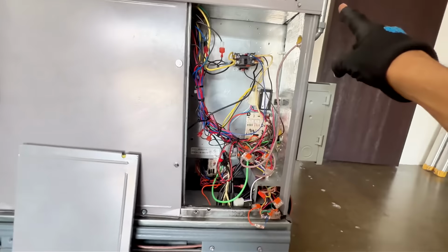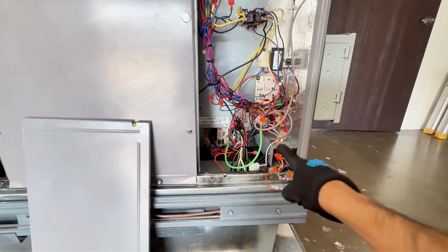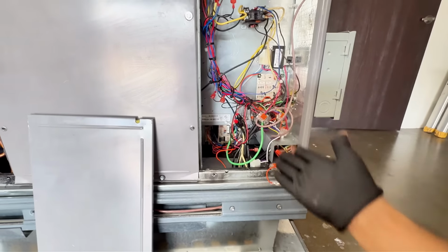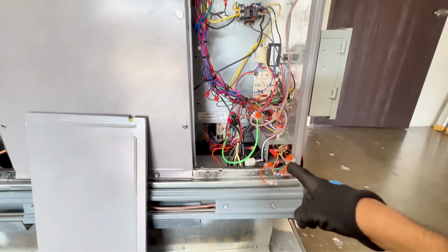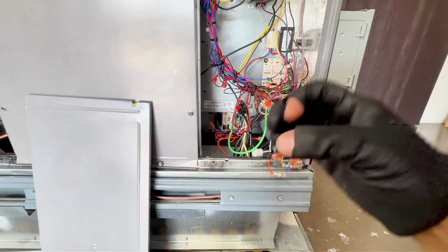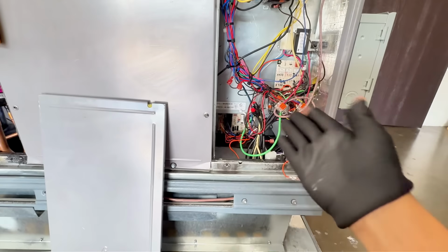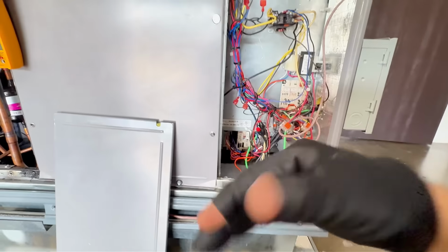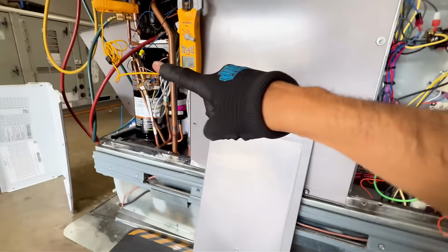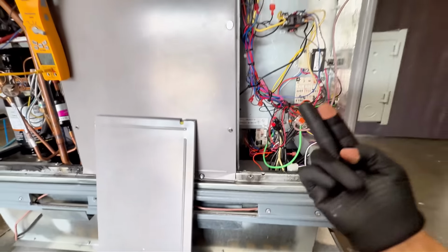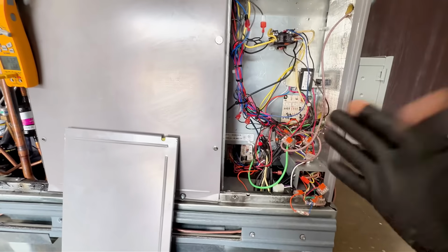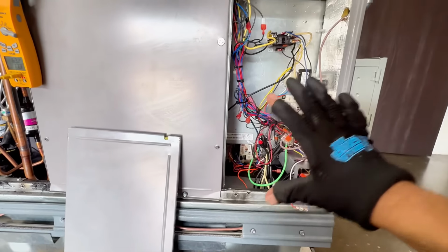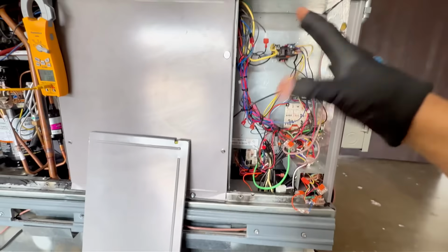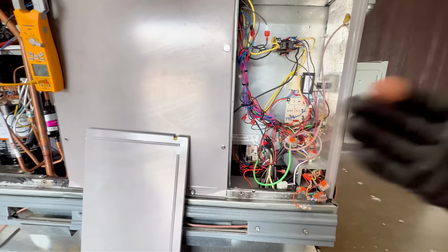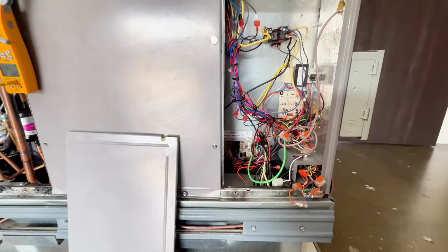So that's why, at the thermostat, make sure you're getting 24 volts between Y and C. And in this case, it's a heat pump, so O and C. Make sure to take note of the path that 24 volts takes. It's a little bit different on each system, but most go through your pressure switches, it comes back, and then it goes to your contactor coil. Once that's done, you're done with the low voltage stuff, because on conventional systems it's 24 volts going to your contactor coil.